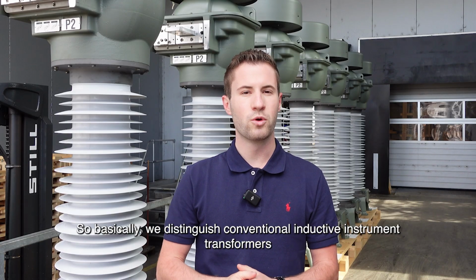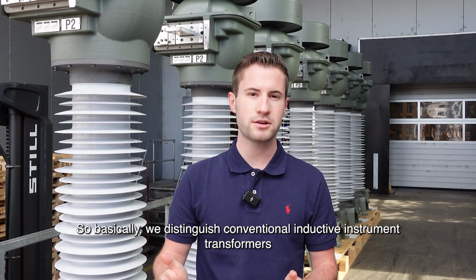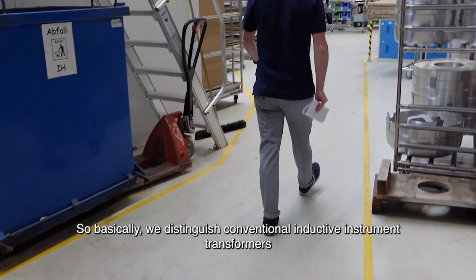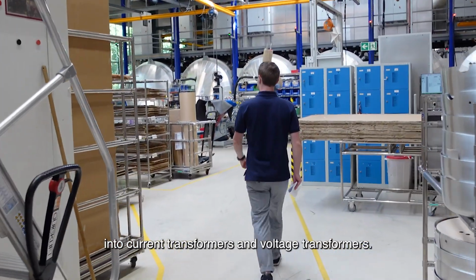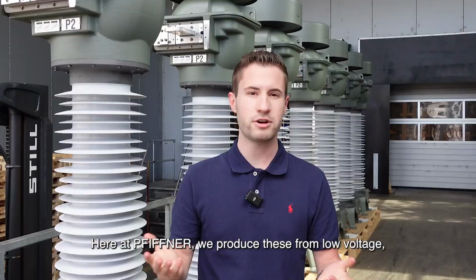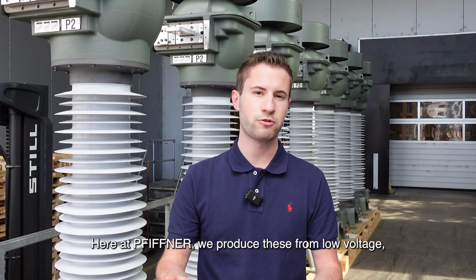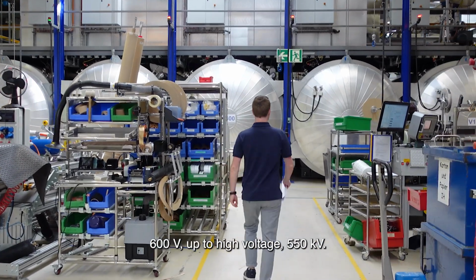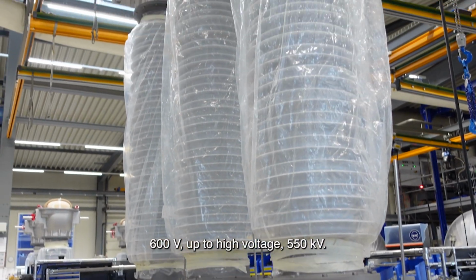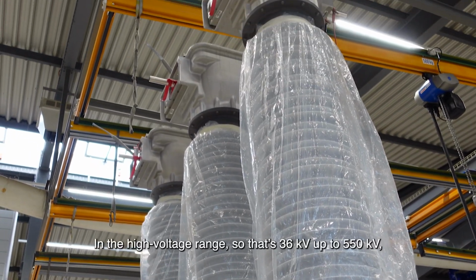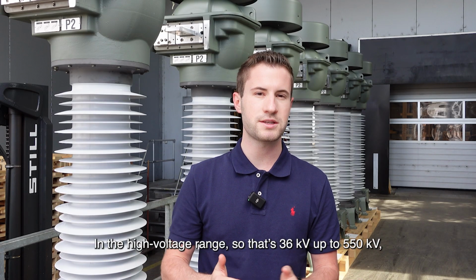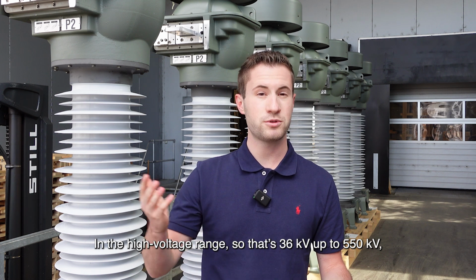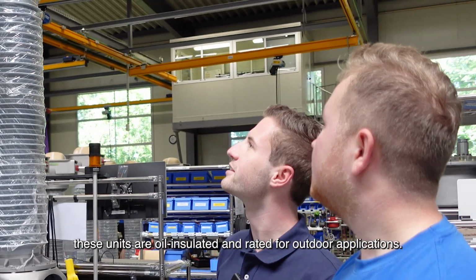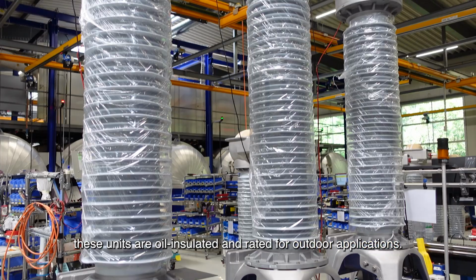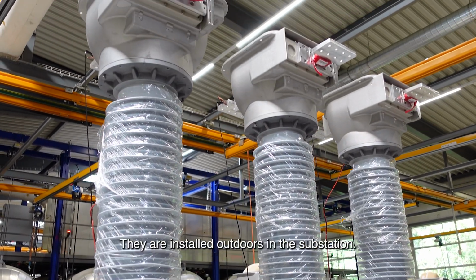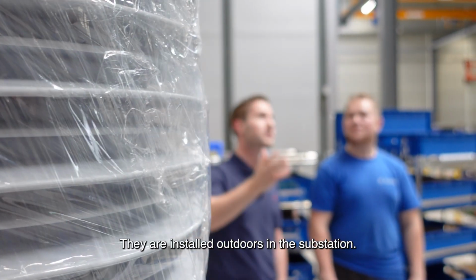Basically, we distinguish conventional inductive instrument transformers into current transformers and voltage transformers. Here at PFIFFNER, we produce these from low voltage, 600 volts, up to high voltage, up to 550 kilovolts. In the high voltage range, that's 36 kV up to 550 kV, these units are oil insulated and rated for outdoor application, installed in the substation.